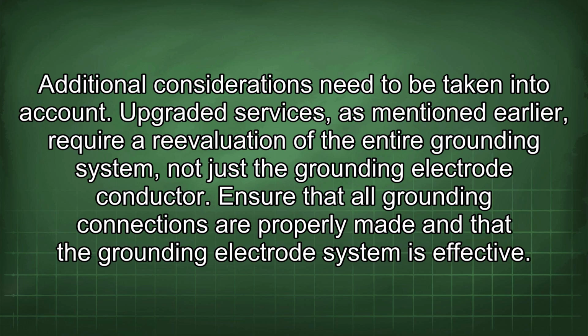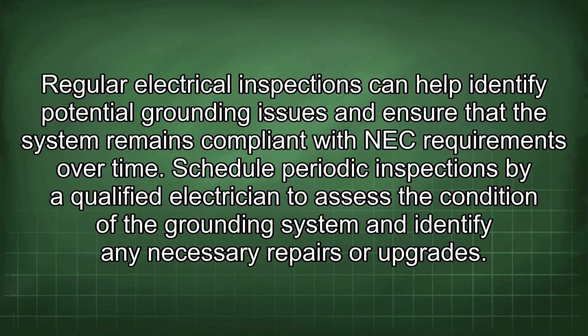Upgraded services, as mentioned earlier, require a re-evaluation of the entire grounding system, not just the grounding electrode conductor. Ensure that all grounding connections are properly made and that the grounding electrode system is effective. Regular electrical inspections can help identify potential grounding issues and ensure that the system remains compliant with NEC requirements over time.